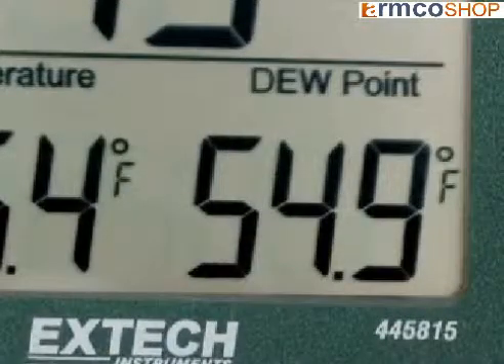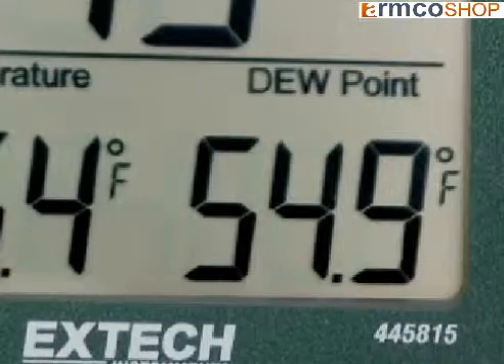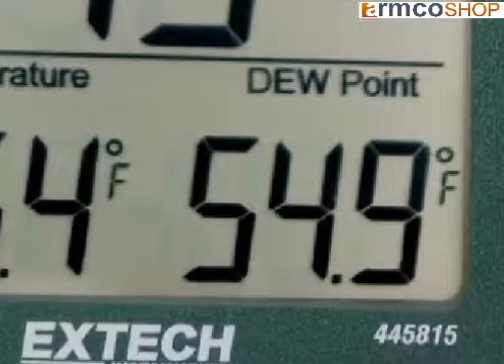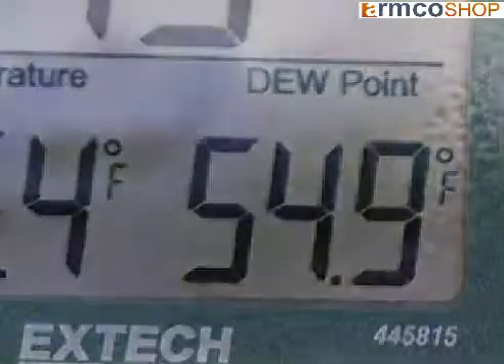The 445815 also displays the dew point. Dew point is the temperature where the air becomes saturated with moisture. The closer the air temperature is to the dew point, the more likely condensation will form on surface areas. Condensation can be very harmful to chemicals, building materials, and any organic material where mold can form.